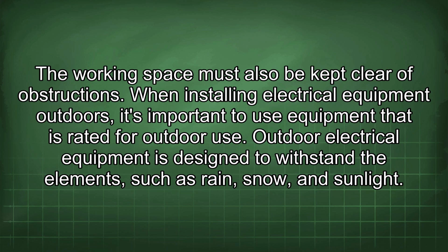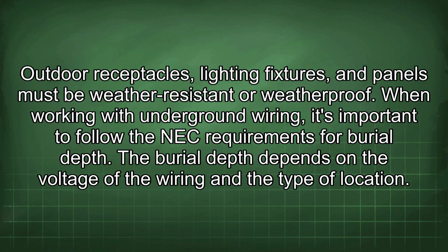When installing electrical equipment outdoors, it's important to use equipment that is rated for outdoor use. Outdoor electrical equipment is designed to withstand the elements such as rain, snow, and sunlight. Outdoor receptacles, lighting fixtures, and panels must be weather-resistant or weatherproof.